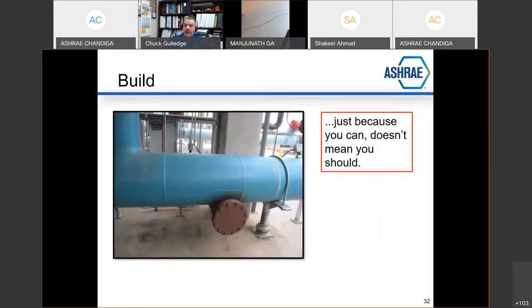Well, this is interesting. Look at this beautiful, beautiful condenser water pipe. It's about 18 inch diameter. Somebody came along and cut that section of pipe out, made a half pipe, made another half pipe, re-welded it all together, and then they stuck this really weird pipe saddle off the bottom going this way. This was a major 4,000 ton cooling tower plant for a chiller plant. It used to have side stream centrifugal separation and zero water loss component, and it was working so well that the facility manager got tired of pulling bags out and disposing of the debris like it was supposed to do, and it was keeping debris out of the cooling towers. He paid somebody to come in and rip all that out and put a sand filter in and blowdown scenarios.